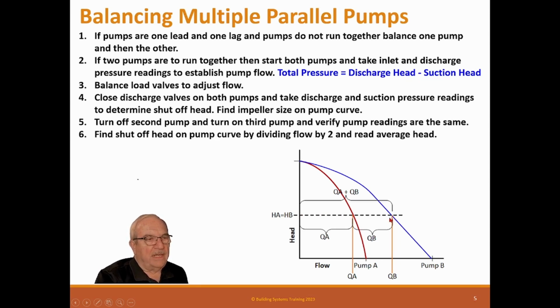I did have a project one time, which was a retrofit project for a big civic center, and it had 8 secondary pumps, which means that 8 pumps were just spinning. It wasn't actually doing anything. They didn't do it on purpose. It had a whole bunch of remodels, and every time they remodeled, they'd add a space and add another secondary pump. It made sense to them, but really they were headers, so it was very bad. The right choice would have been to put bigger pumps in and still have 3 pumps. Anyway, that's how you do parallel pumps.